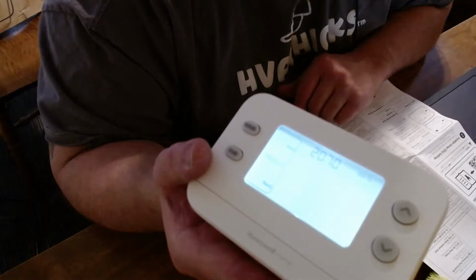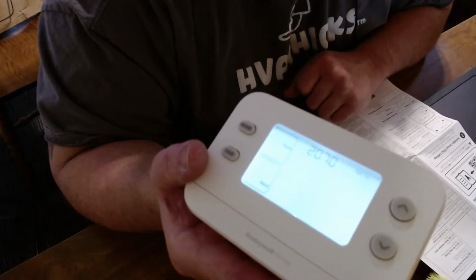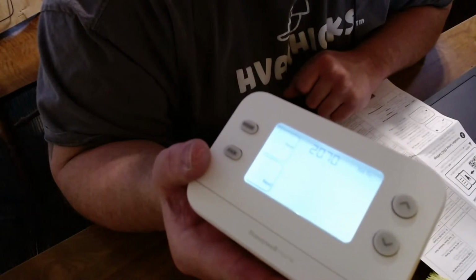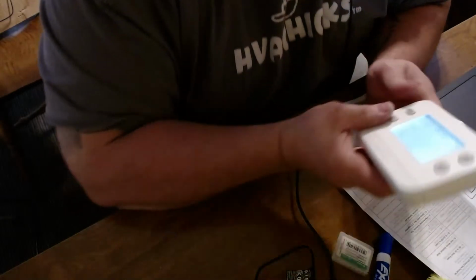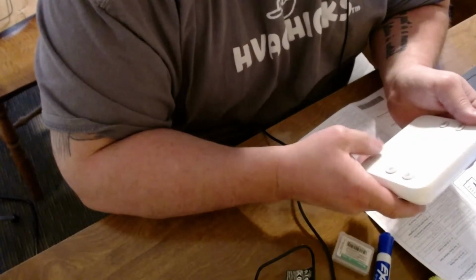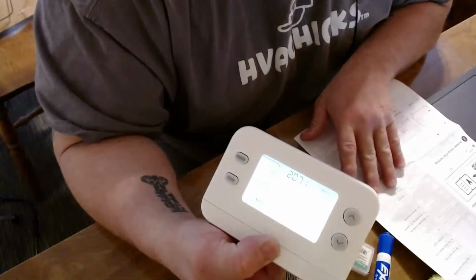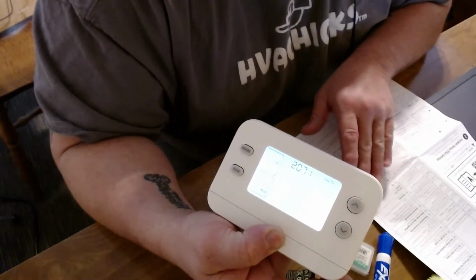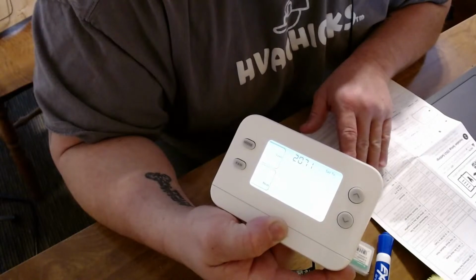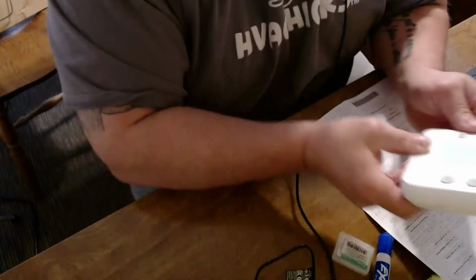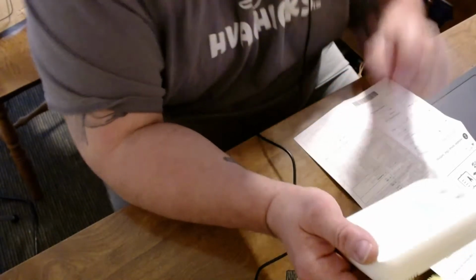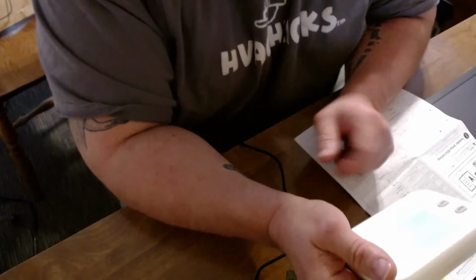Our next setting is 2070. 2070 says heat stages, backup heat stages. Heat stages 1 or 2, backup heat stages 1. So we're going to set this as a 2-stage heat. 2071, backup heat stages. Excuse me, I set that for cooling as 2070 for 2 stages of cooling, and we're going to set it for 2 stages of heating. So we're going to use a Y1, Y2.